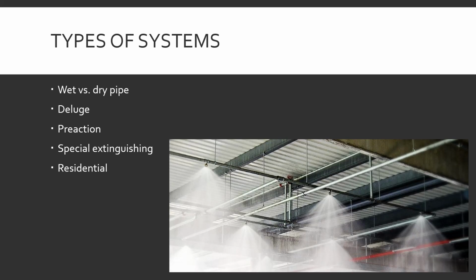Where this helps keep accidental damage down is, let's say our forklift driver hits one. Well, they hit a sprinkler head, and the system will go, okay, I got a sprinkler head open, but nothing else is telling me to do anything. So it'll send out an alarm, it'll trip kind of a pre-action alarm. Where there's a certain amount of time for building maintenance to go, oh no, someone hit the sprinkler system. I don't want to damage all the stuff. I got a few minutes to go tell the system everything's cool. Don't go off. Fix the sprinkler head.